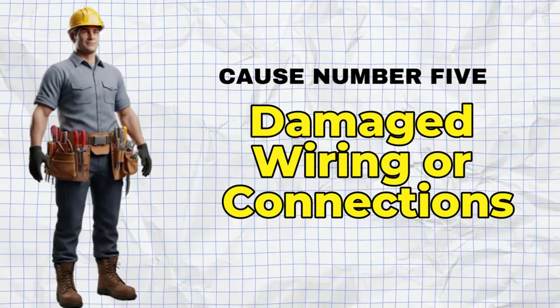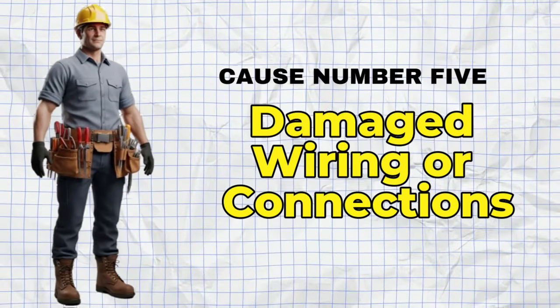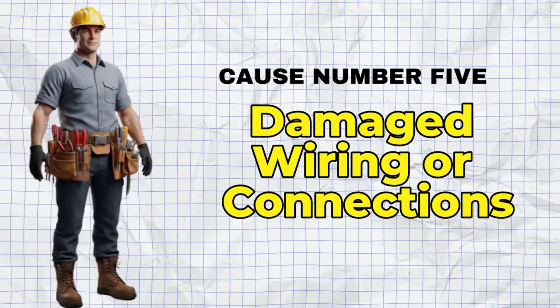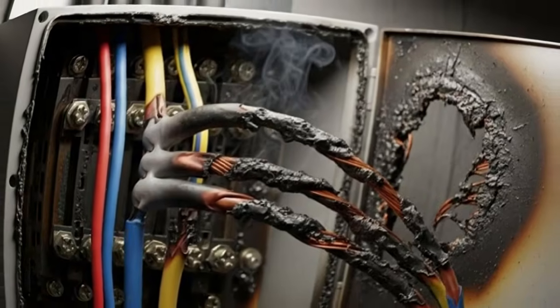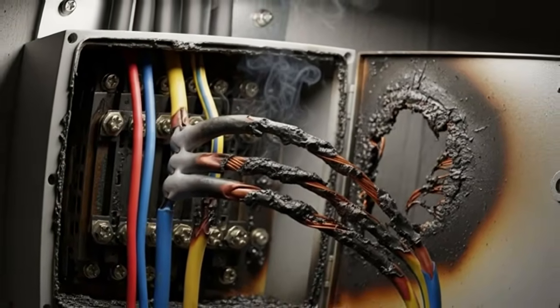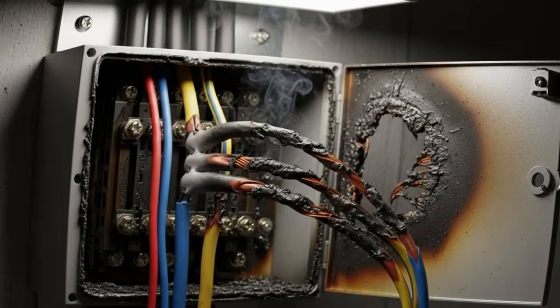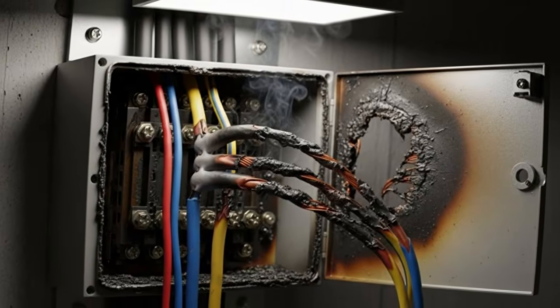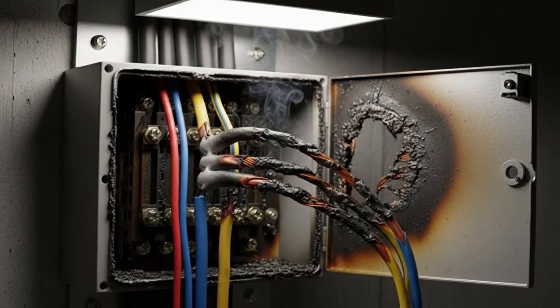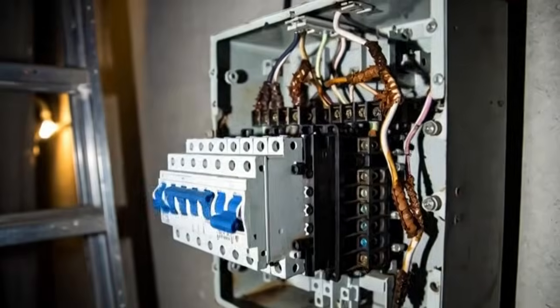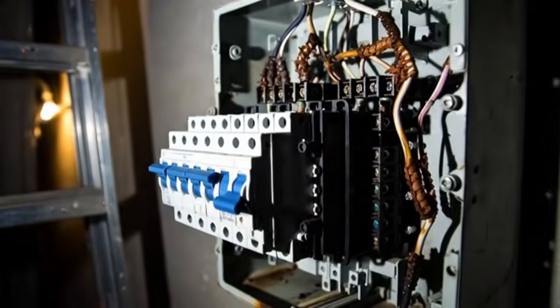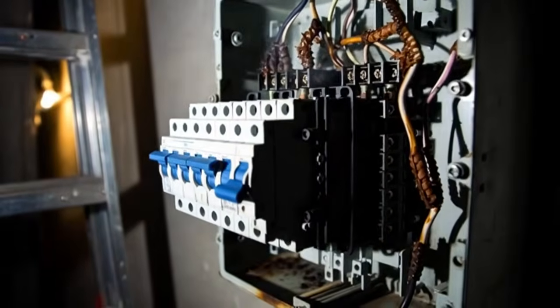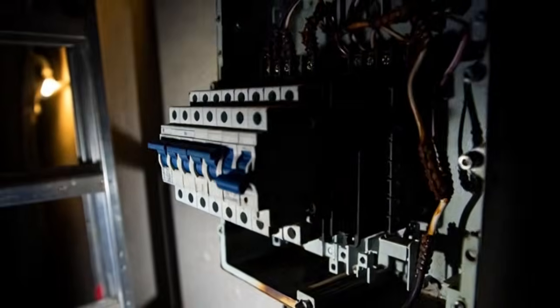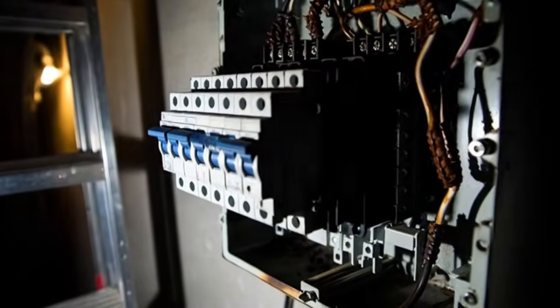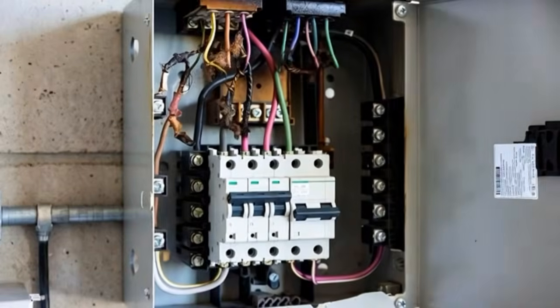The fifth cause looks beyond the breaker and the immediate fault to the wiring infrastructure itself. Wiring damage accumulates over time. Connections loosen from thermal cycling. Wire insulation degrades from heat exposure. Rodents chew through cable jackets. Nails and screws puncture wires hidden inside walls. Previous homeowners or unqualified workers create hazardous splices and connections.